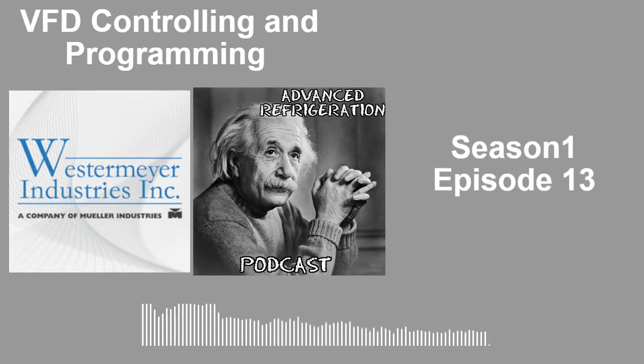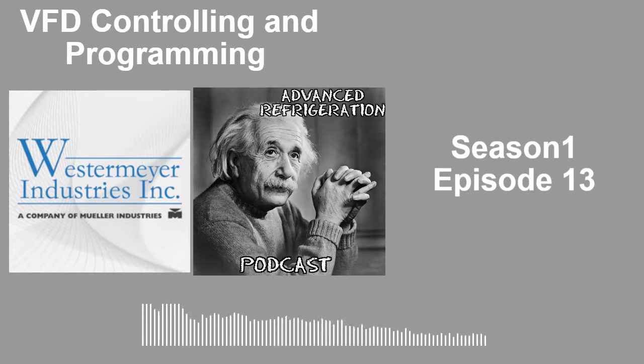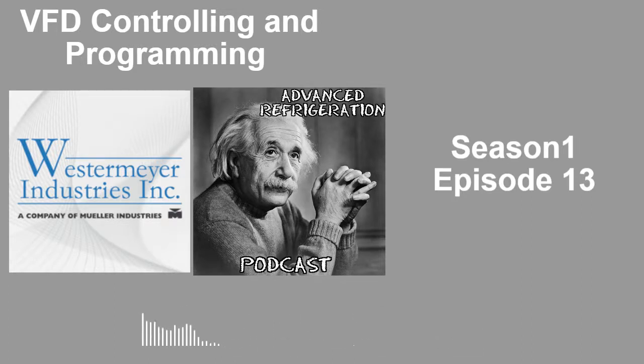So if you're out and you got a bad transducer at a Walmart on a condenser, and it's got a Danfoss transducer on there, or a Novar transducer, and you only got a CPC transducer on your truck for the drive, you could change it, as long as that transducer is not also supplying the condenser control board. You could just take that transducer, put a CPC one in there, and reprogram it, and that drive will work fine.